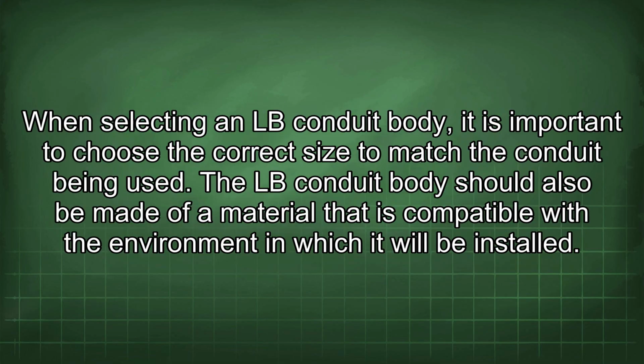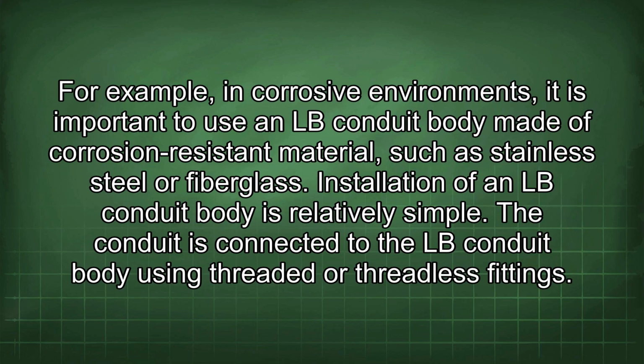When selecting an LB conduit body, it is important to choose the correct size to match the conduit being used. The LB conduit body should also be made of a material that is compatible with the environment in which it will be installed. For example, in corrosive environments, it is important to use an LB conduit body made of corrosion-resistant material such as stainless steel or fiberglass. Installation of an LB conduit body is relatively simple.